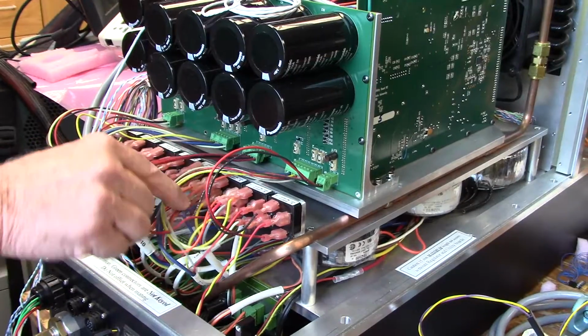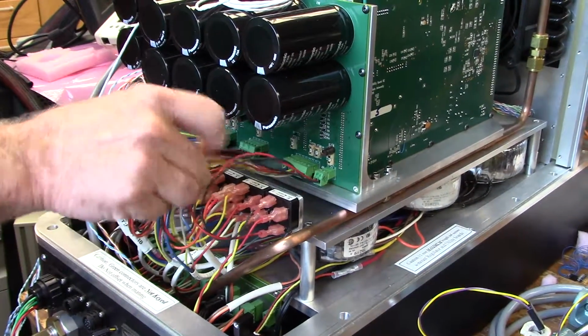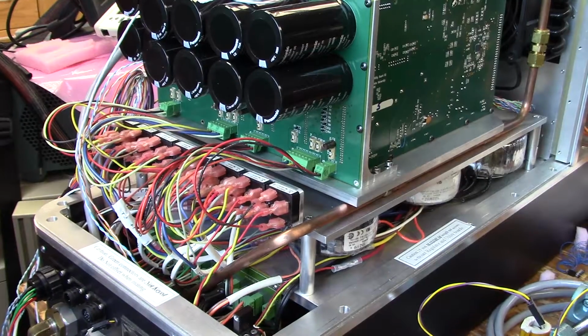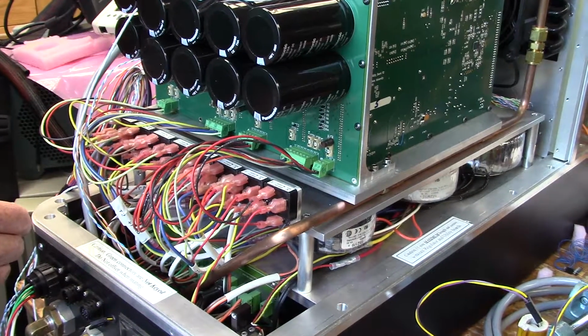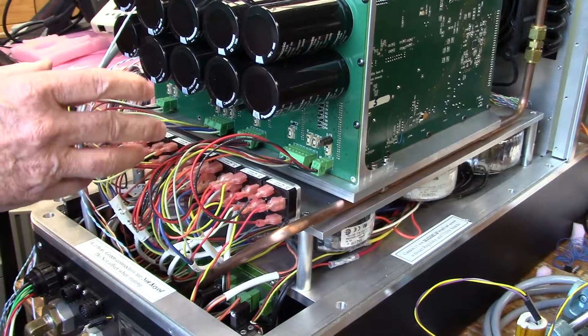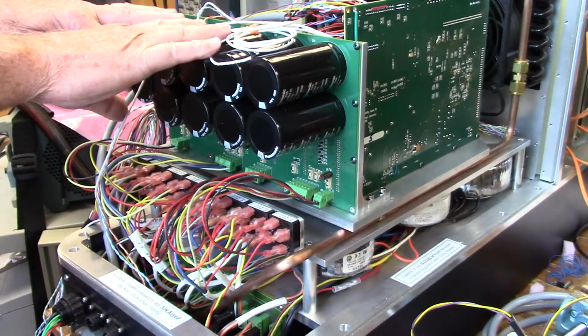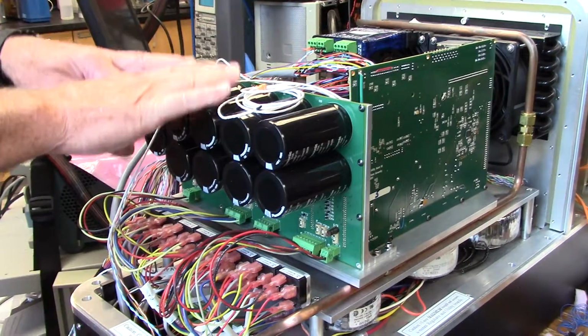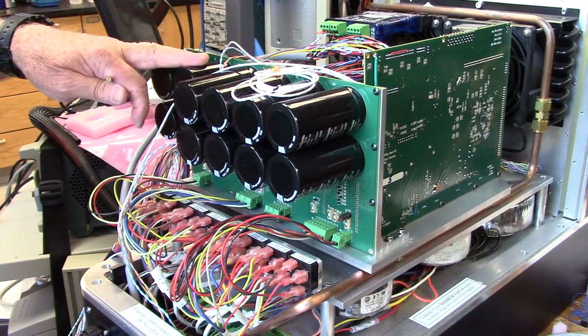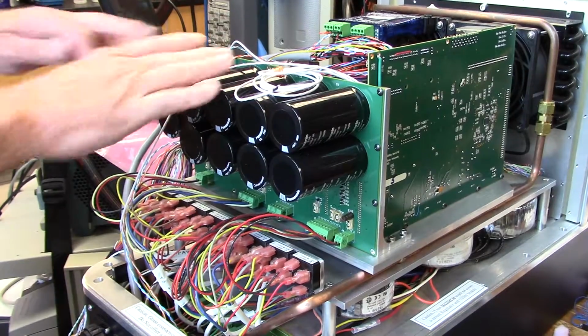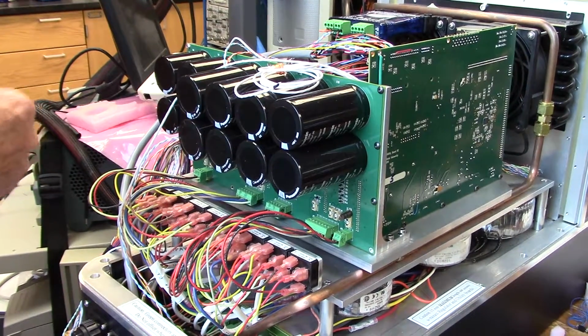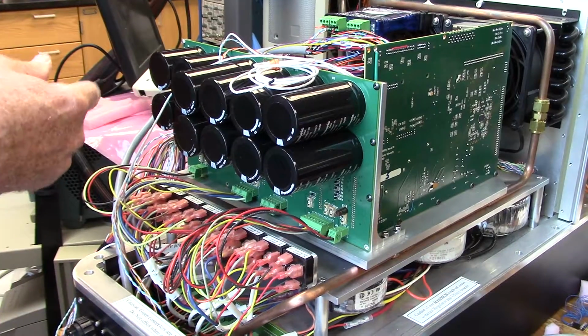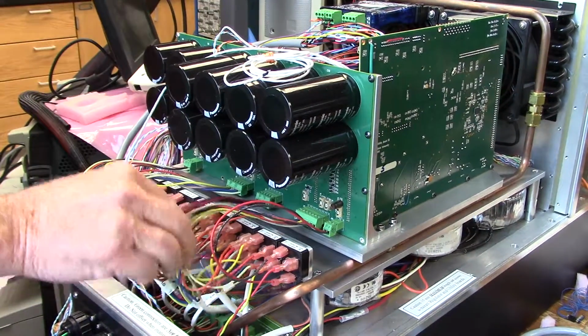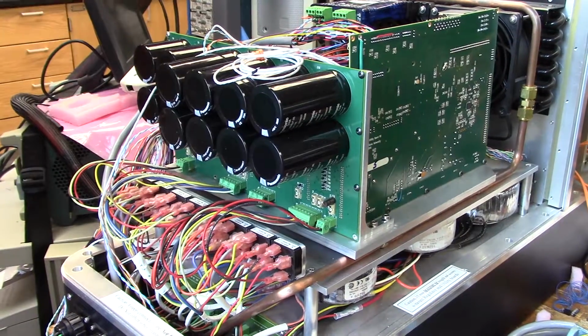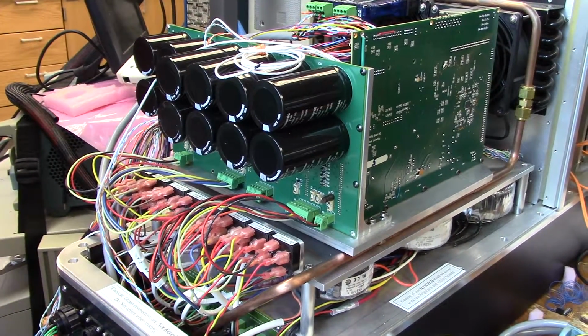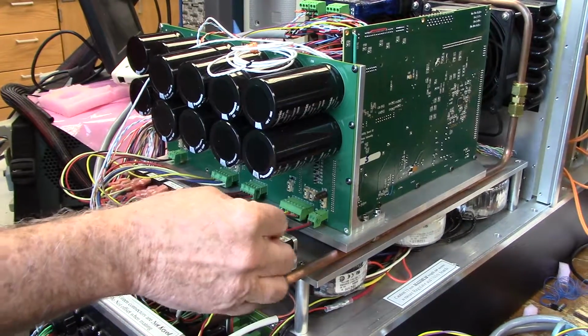The output from the bridge rectifiers comes through these cables, 1, 2, 3, 4, 5, to more green plugs, carrying the unfiltered DC to the capacitor board, where all the DC filtering is done — at least for the science and guide array. That way all the AC currents circulating on this wiring stay here and don't go farther upstream into the box, getting rid of the line frequency AC currents quite nicely.